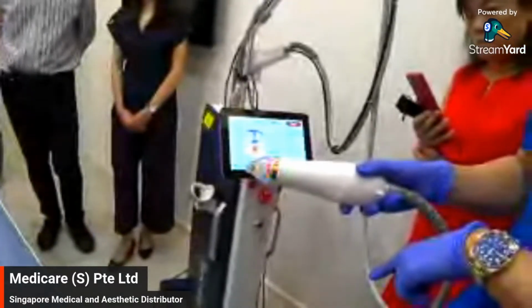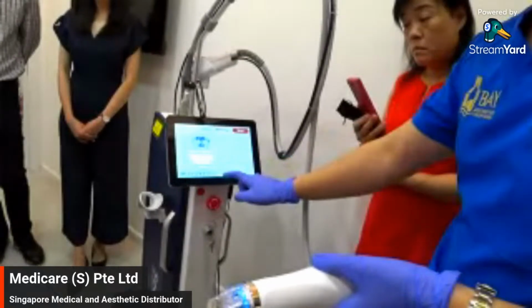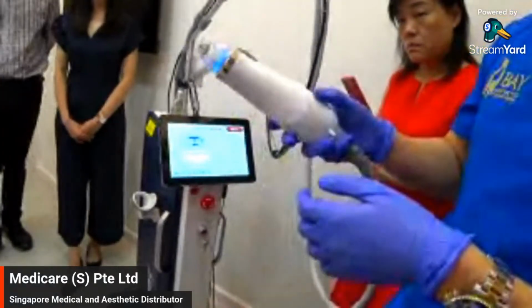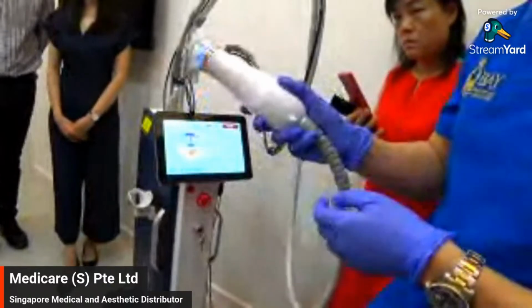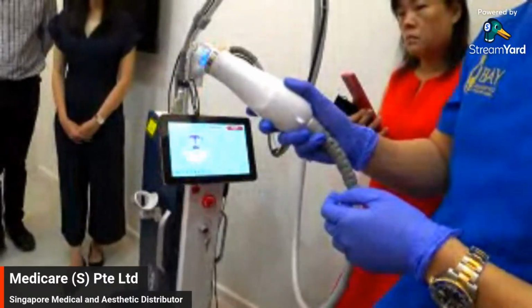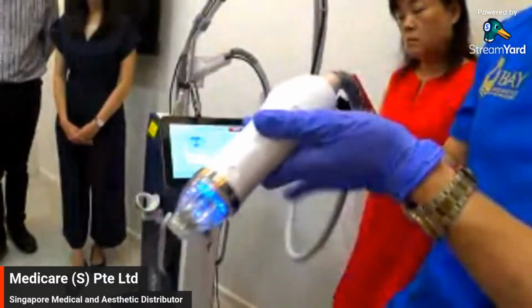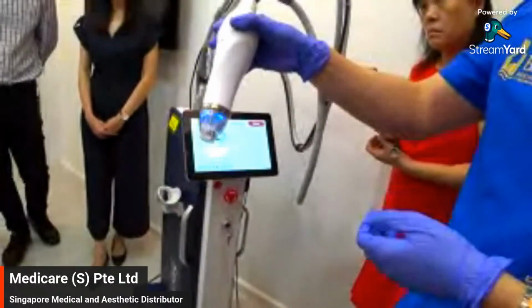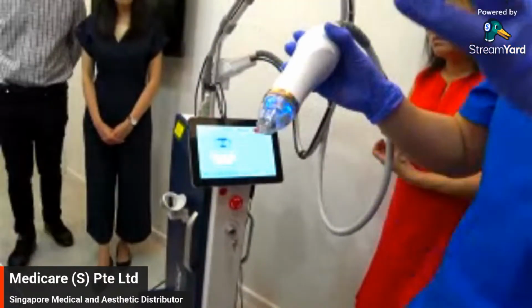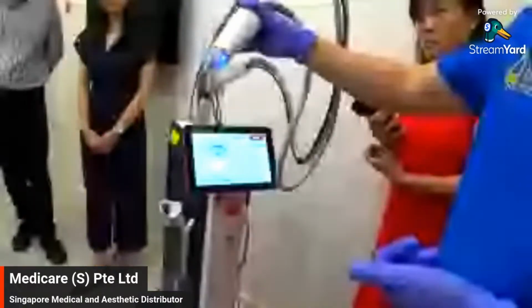Okay, and let's say I'm a bit more experienced, I will set it at maybe 0.2 seconds. So when I fire, as you can hear, I have 0.2 seconds to get into position for the next shot. But of course, if I don't get in time, then I risk burning the patient. And if I rush, I may scratch the patient.